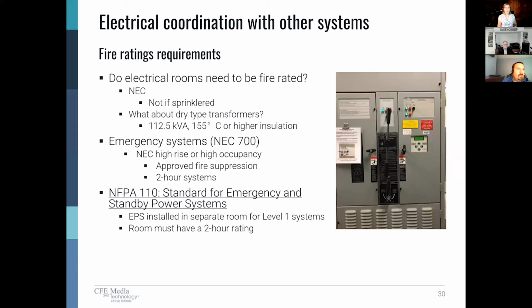And then there are some occupancies, specifically NEC high rise and high occupancy, like assembly occupancies, that would trigger the requirement for approved fire suppression and 2-hour systems to be installed. And then NFPA 110, which is the standard for emergency and standby power systems, also imposes some additional requirements in certain installations. The transfer equipment must be installed in a separate room for level 1 systems. So for example, a hospital where you've got an essential system, you have interior generators, and you've got incoming normal distribution, the transfer switch equipment needs to be located in a separate dedicated room, and that room needs to be 2-hour rated.